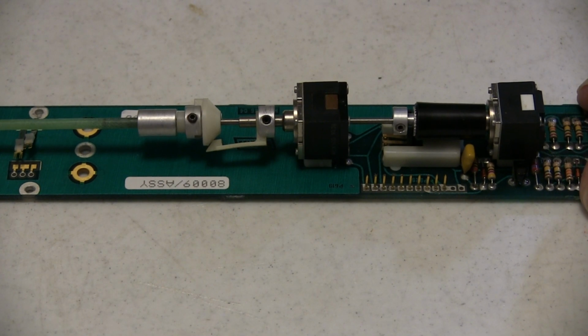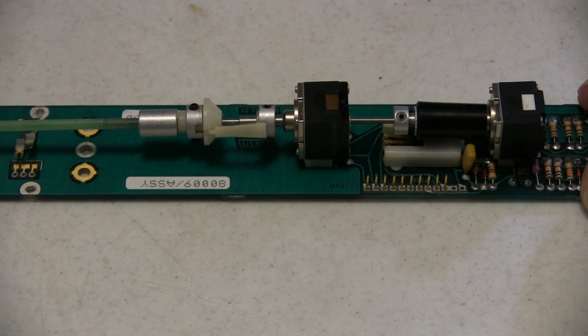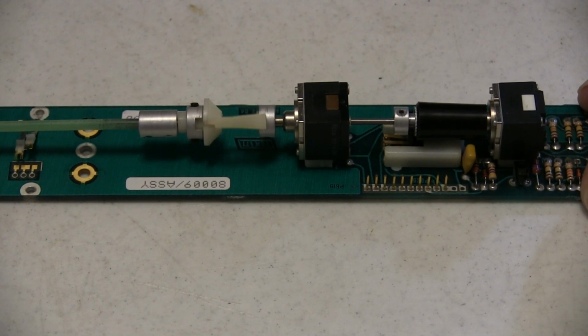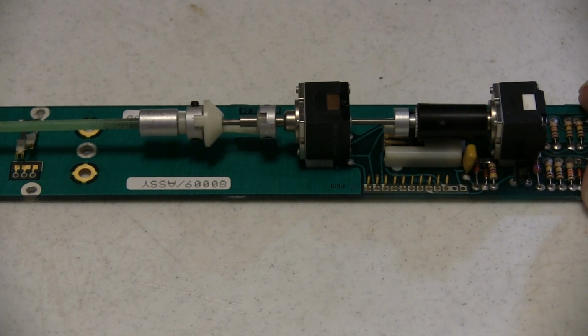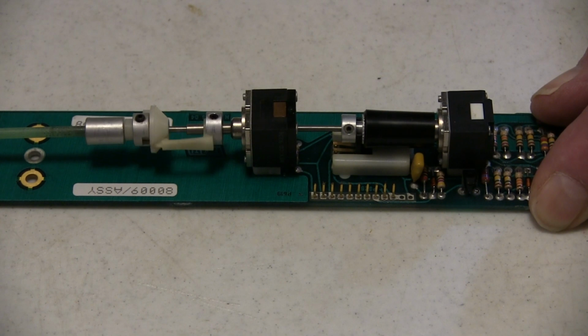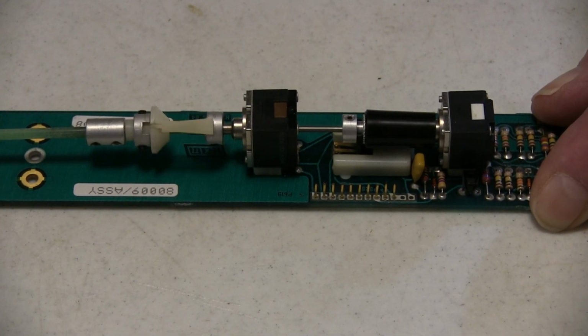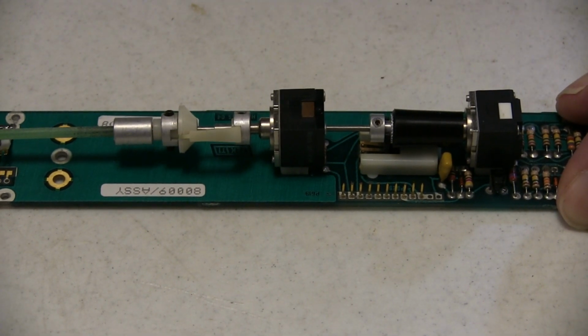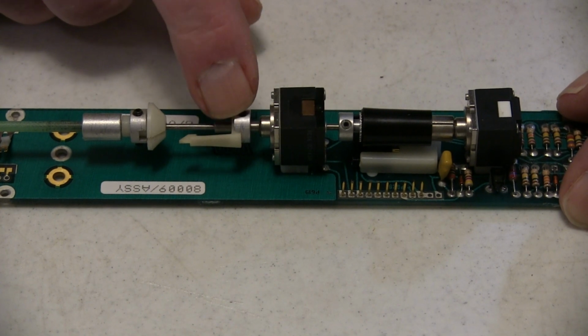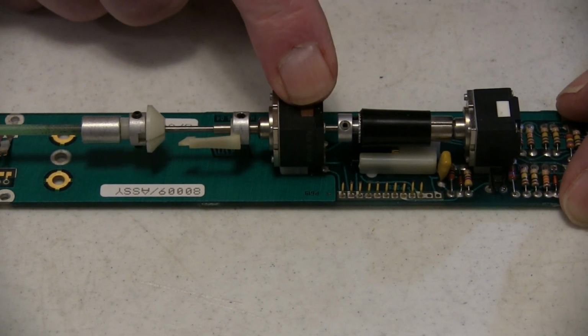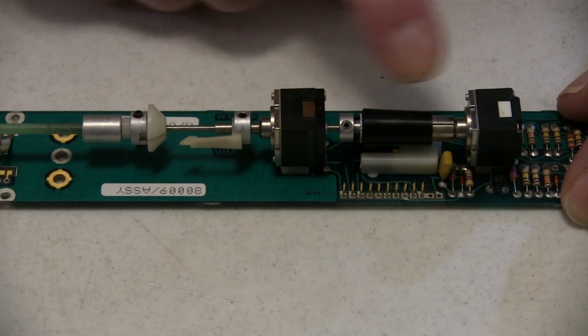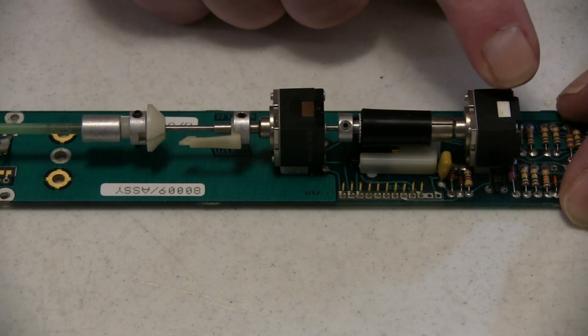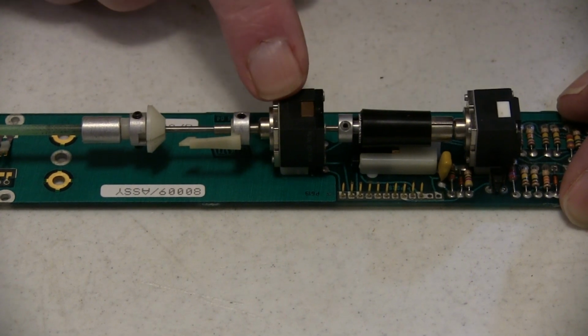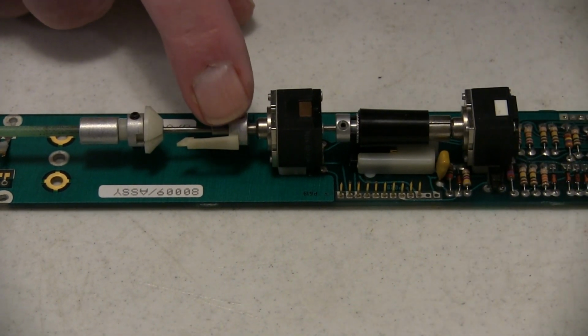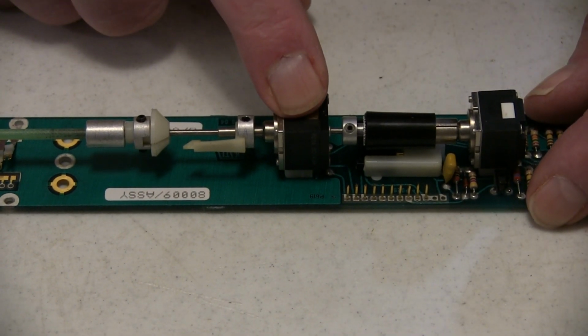But when you push in the variable knob and turn it, eventually the little arm drops into that slot in the cone, and now you are turning the calibration pot. But notice that it's still also turning the variable pot. So the rotation of each pot is actually constrained by the other. So if this little arm here is not in the right position, then the rotation of the calibration pot might be again constrained by the limits on the variable pot, and that's exactly what the problem was. This mechanism was misaligned so that the calibration pot didn't have its full range.